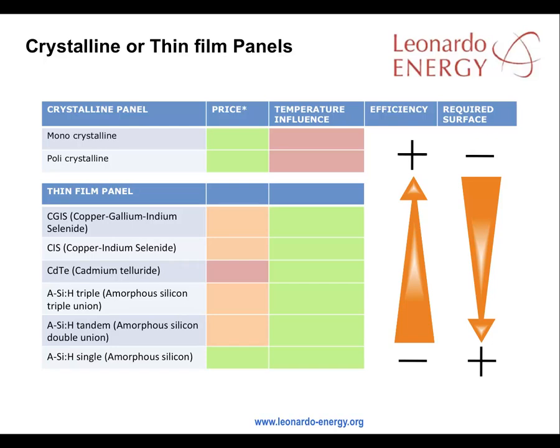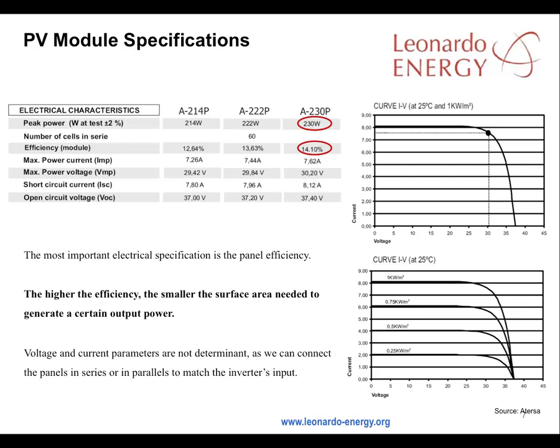Temperature becomes relevant in locations where temperatures are above 25 degrees centigrade. With PV modules, panel efficiency is the most important electrical specification to be checked. The higher the efficiency, the smaller the surface area needed to generate a certain power output. Voltage and current parameters are not determined because the panels can be connected in series or in parallel to match the inverter.